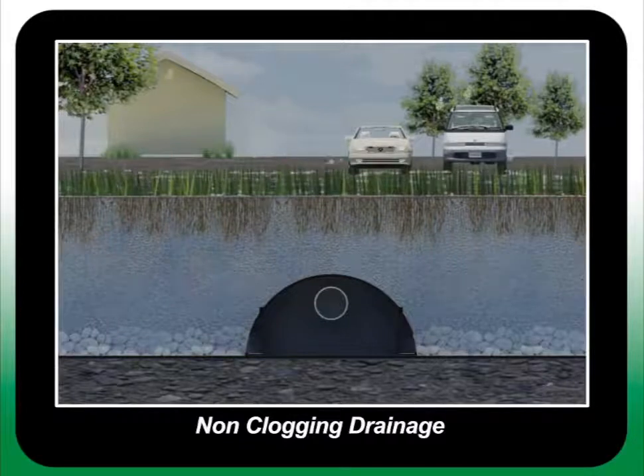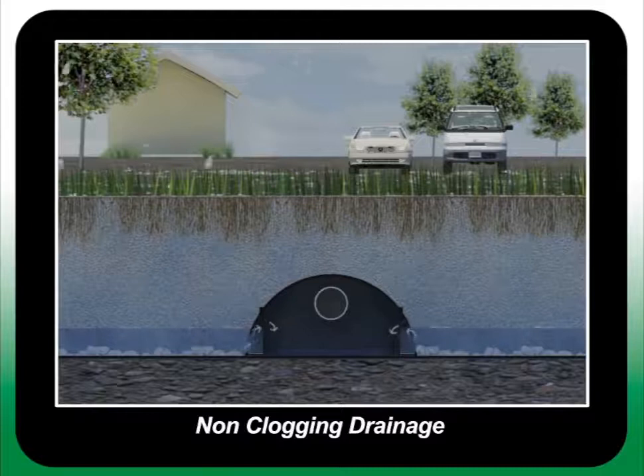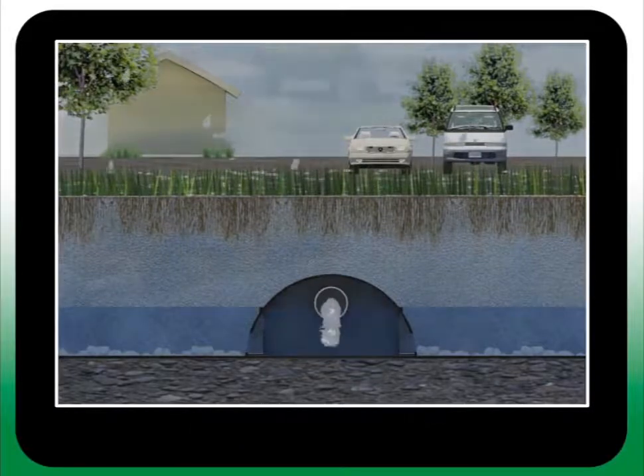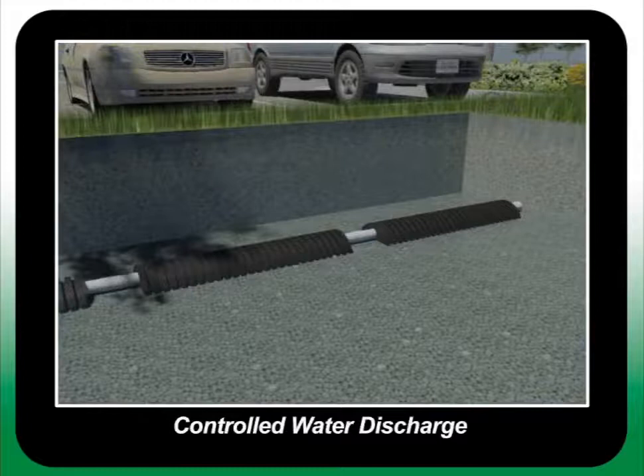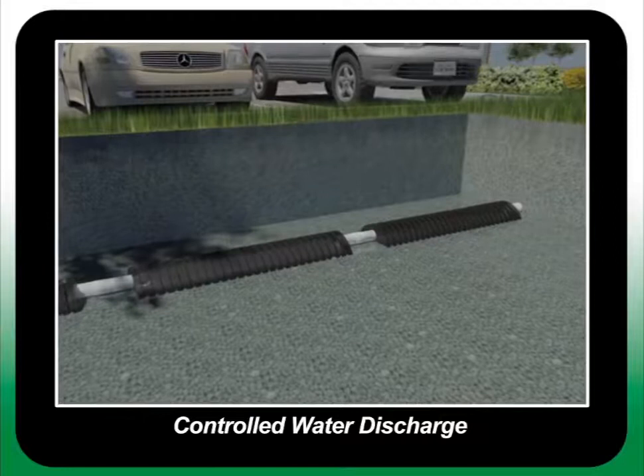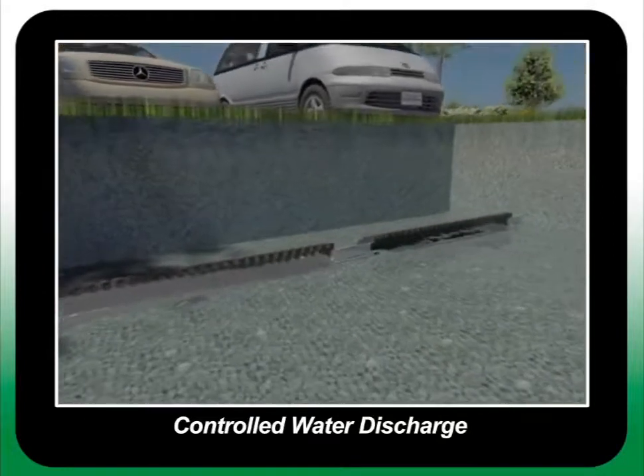As the water moves downward through the sand, into the fine gravel, and through the gravity trap, into the EPIC chamber. When stormwater or surface runoff drains to the system, the sand profile immediately initiates filtration. The chamber and connector pipes distribute the water evenly throughout the system and retain a designed amount of water for irrigation reuse.